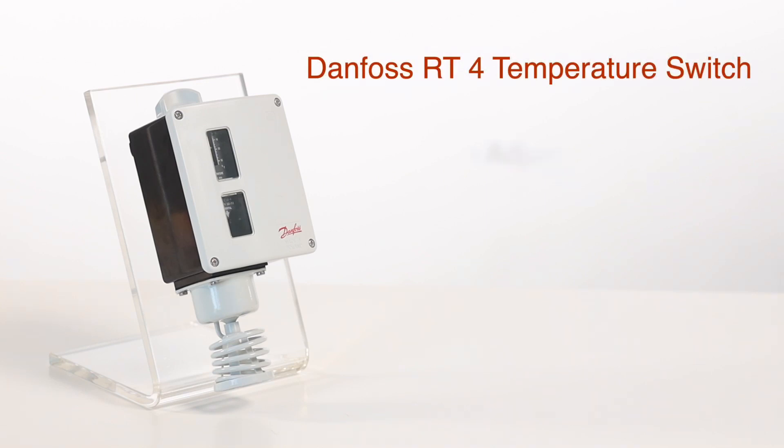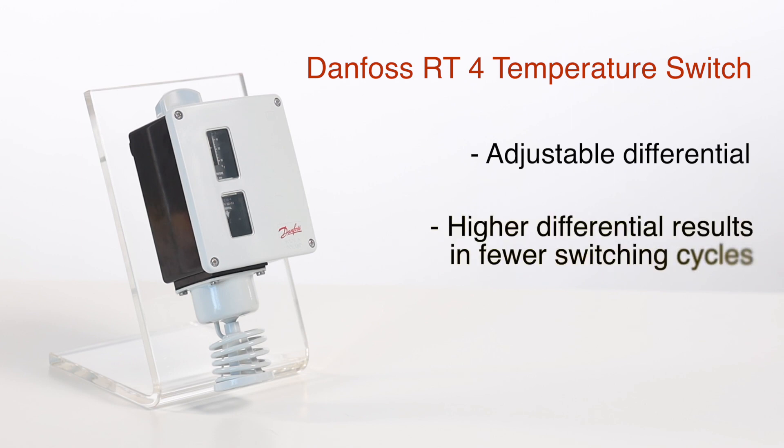On most Danfoss temperature switches, the differential is adjustable. Please remember that a higher differential results in fewer switching cycles and a longer life.